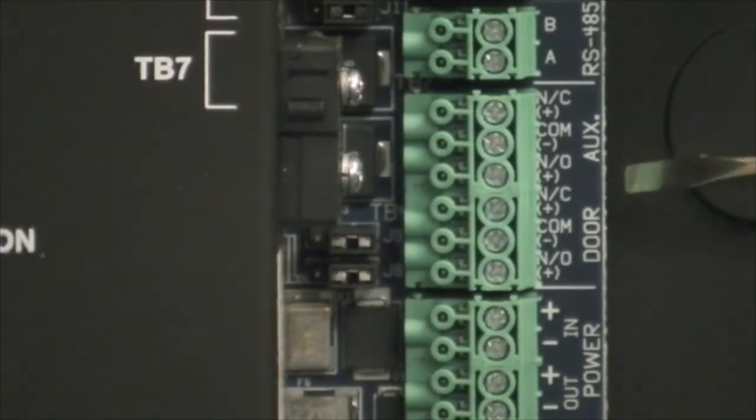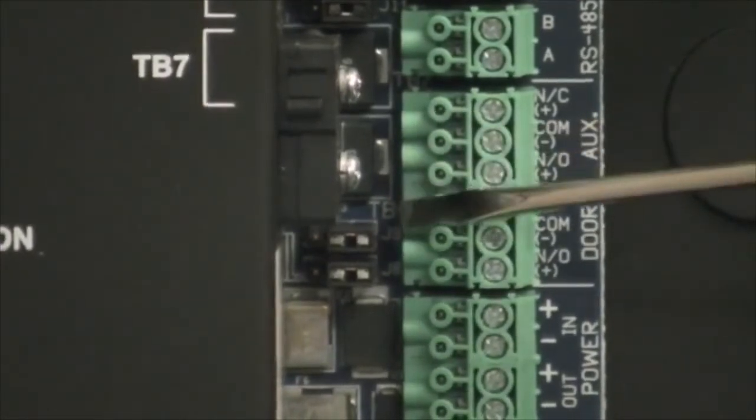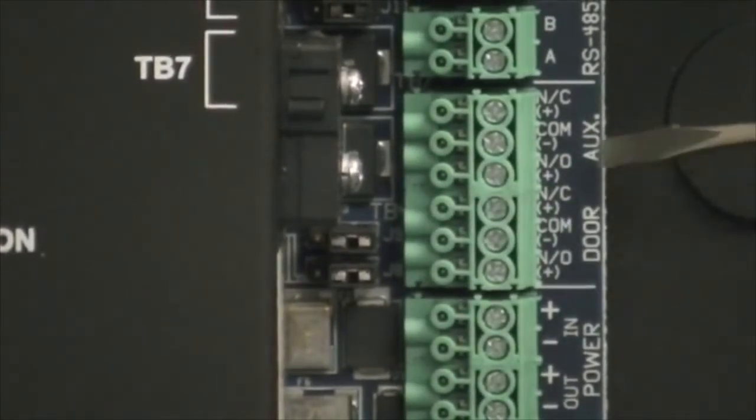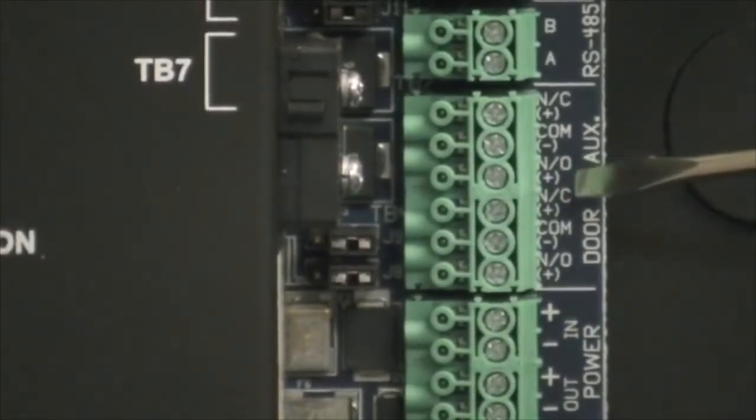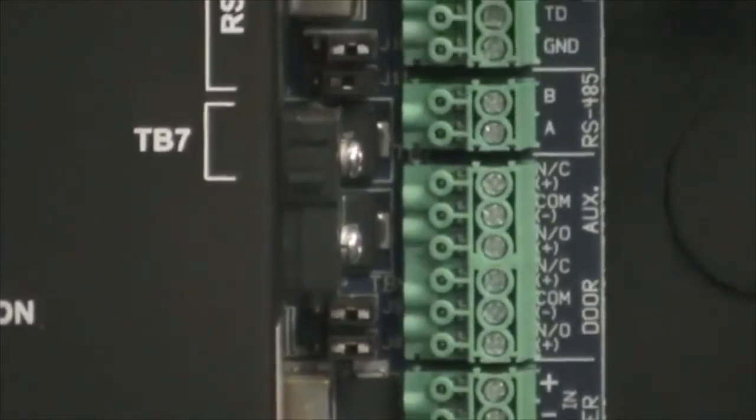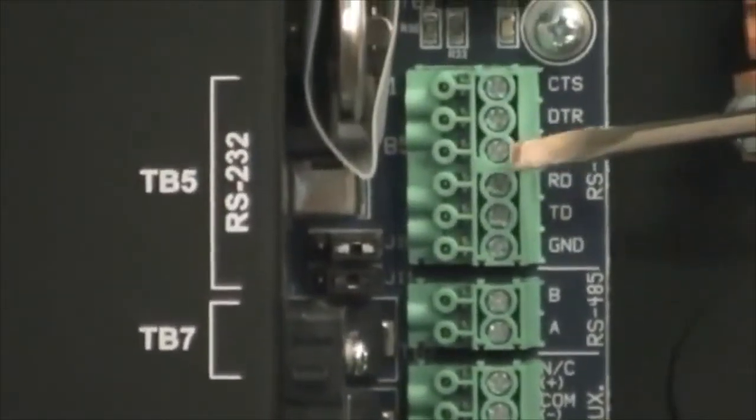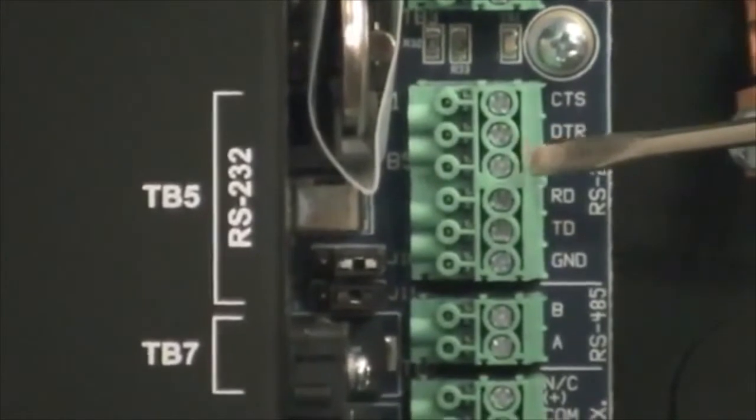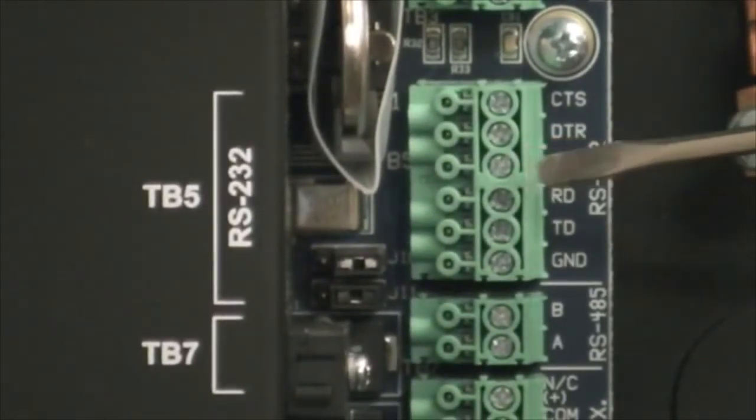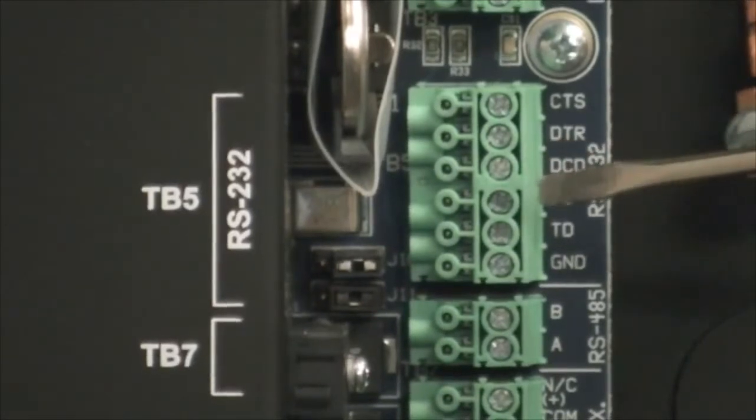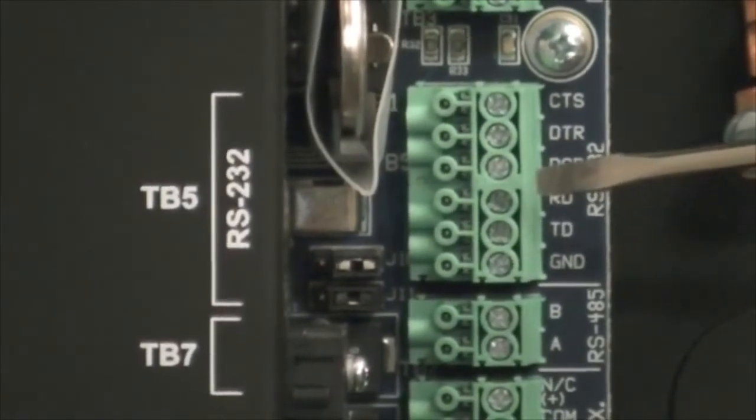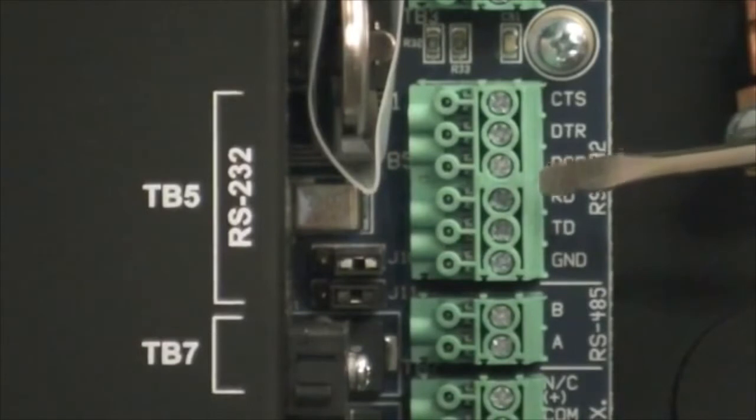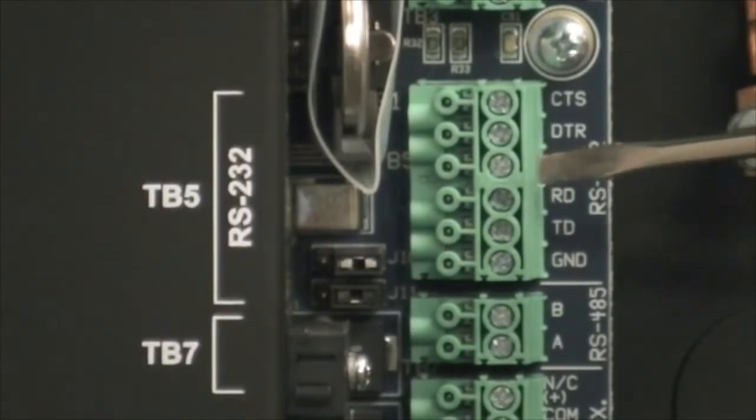As well, through a jumper setting, we can change this to a Form C relay connection. Above that we have an RS-232 connection that can be used to connect to the CA-150 serially or program the CA-150 serially as well. The CA-150 KHS does not require you to do any programming for communications as the unit comes pre-programmed for Keyscan entirely.